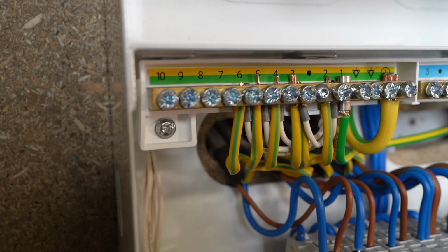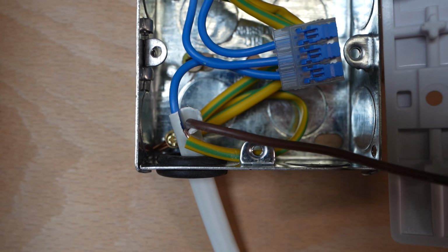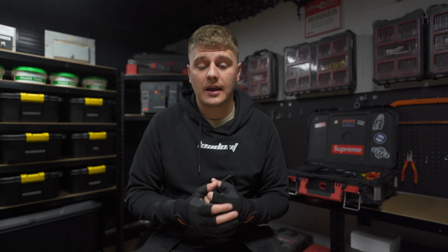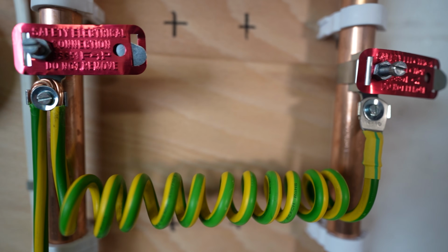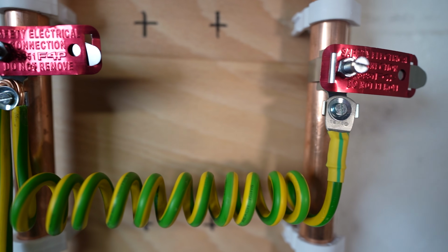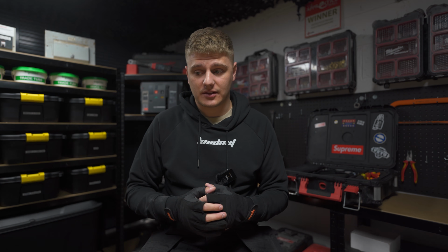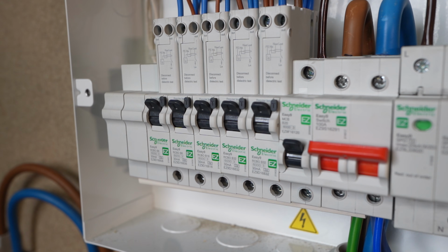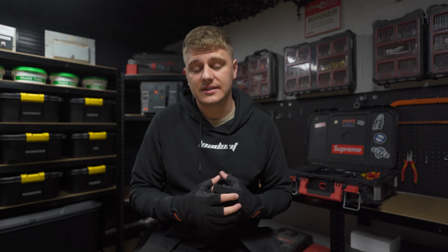Earthing conductors provide a path to earth for fault currents, which protects people and the like, but also gives the protective devices the ability to trip and operate as intended. Bonding conductors ensure that extraneous conductive parts are at the same potential as the electrical installation. That's whether under normal conditions or fault conditions, it just ensures that they're at the same potential. And it also provides a low impedance path to earth so that, under fault conditions, again, circuit breakers and switchgear and stuff can operate as intended.